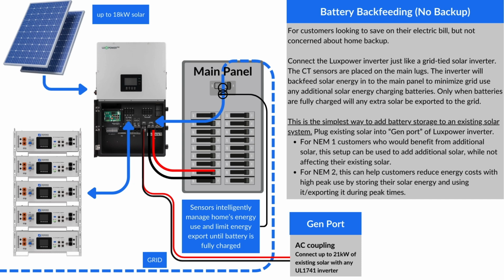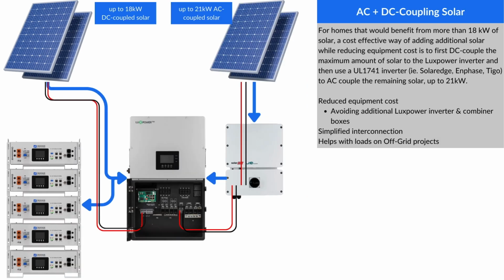And based on the size of the solar and the battery system, you can still achieve 80, 95% of self-consumption by doing this method. And then the last diagram that I'll show you here is a common question we receive from customers and installers: what's a simple way to add battery storage to existing solar systems? And this inverter makes it very simple by using the generator port for AC coupling. Any inverter that's 1741 listed, you can just take the connection points into the main panel and redirect them into the generator port of the inverter.